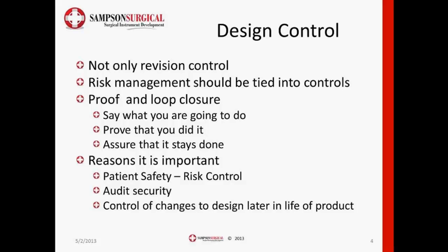And of course, that same methodology applies when we go to change the design. We want to be sure that when we make a change to the design, we don't break something as part of the development process. So we want a traceability system that allows us to get to the tests that were done to approve it in the first place, so we can redo those tests and make sure we don't break something along the way. So that's the thumbnail sketch of design control.